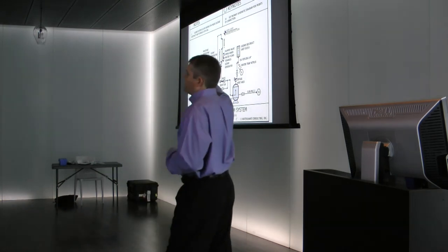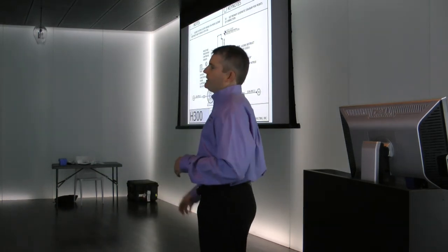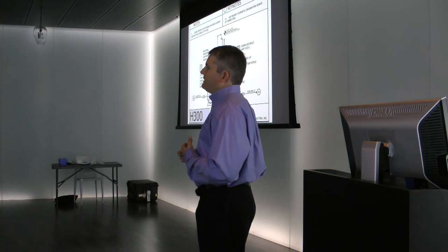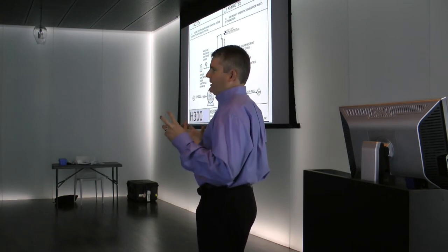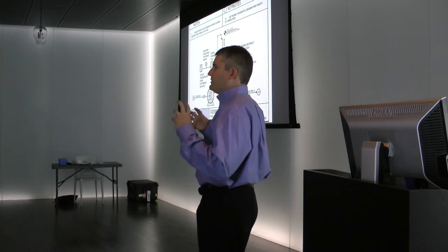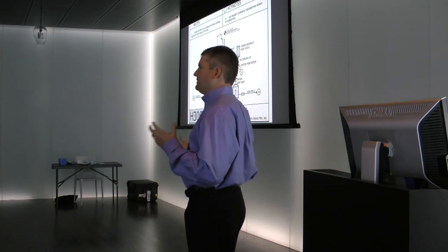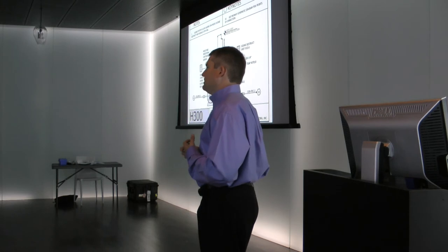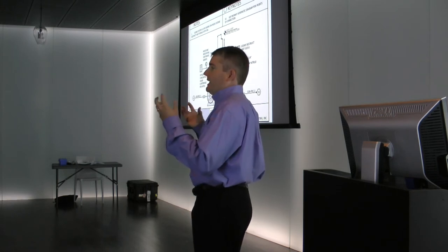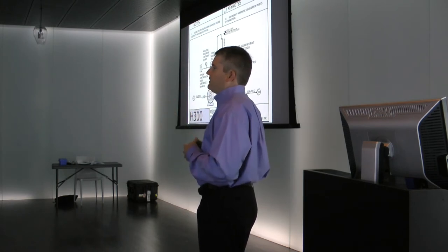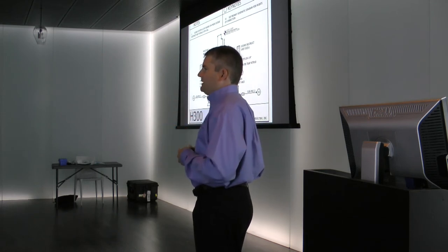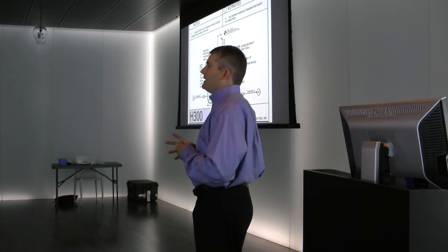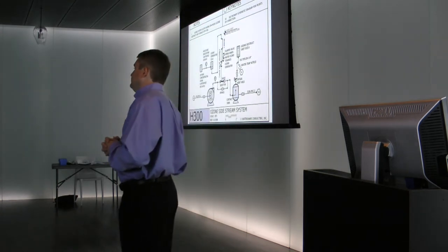The maintenance for the ozone generator is every few months. You want to clean things up. Some companies say once a year you actually want to dismantle the corona discharge cells, clean them out, and reassemble them. It's basically a chamber of lightning, if you will. That's how they created this with a dielectric, and they just create lightning in a tube.